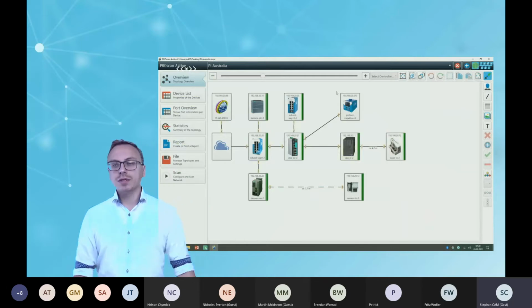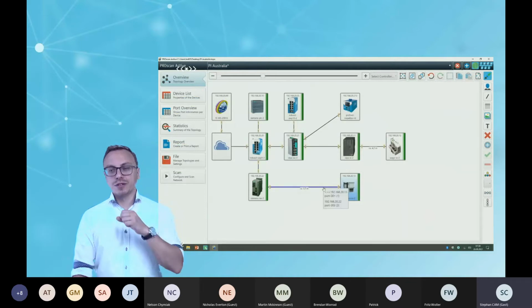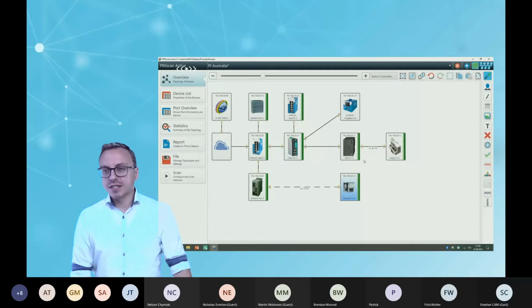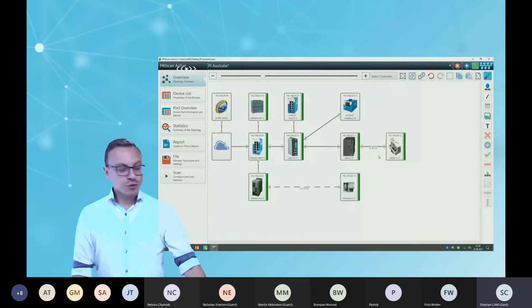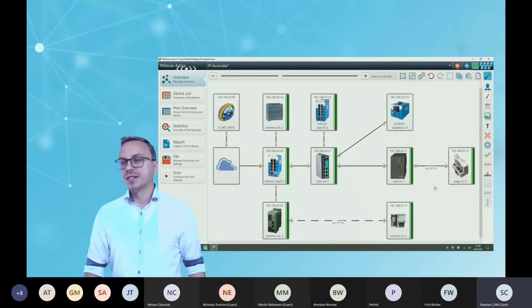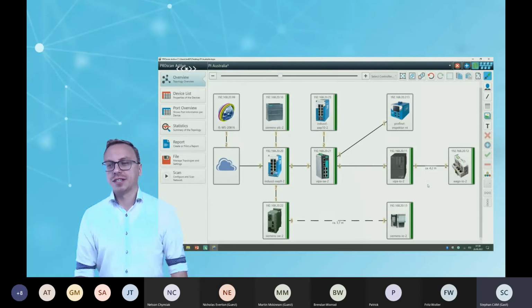ProScan Active can measure the whole topology and will show you what devices you have in the system, and you see what kind of installation you have. For example, here we have a plastic optical fiber installation, so it's a fiber installation, and you can find out here, if the devices support this information, the line length.